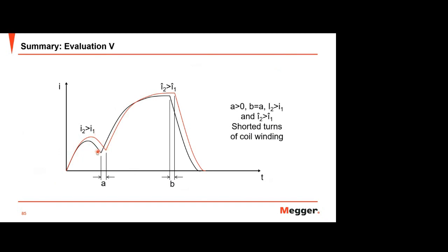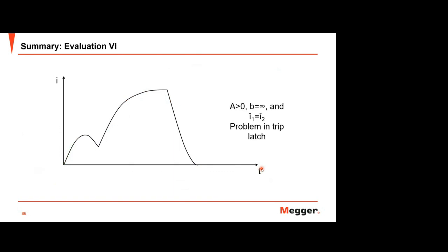If you see the problem start from this first peak of the graph, sometimes this first peak can affect the second current, but sometimes it doesn't. And this one is a problem in the trip latch. As you remember, there is a latching mechanical part that holds the mechanical breaker. So if there is an issue with that, you can see something similar to this. At the end, the breaker will not operate, because it doesn't finish the process to the buffer position. So the coil plunger just touches the latching, but the latching doesn't move. And if the latching doesn't move, the breaker will not operate.